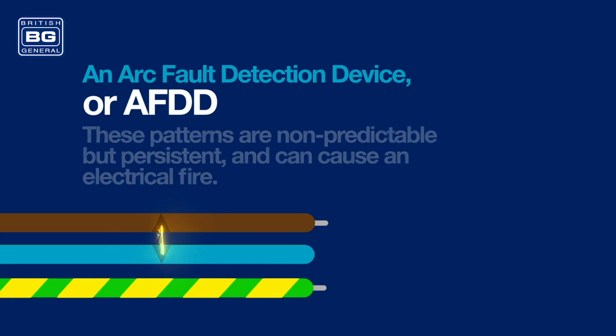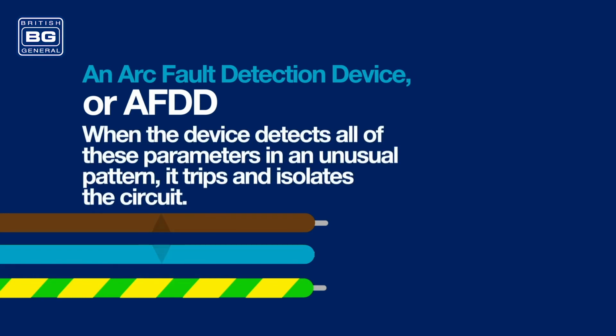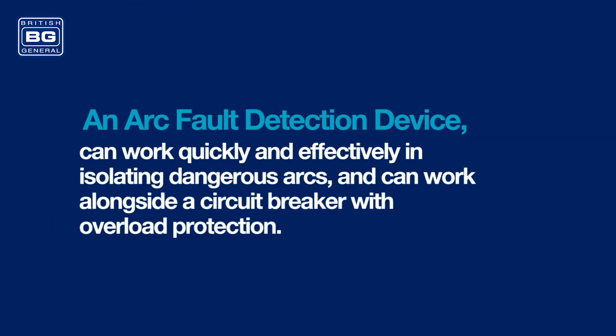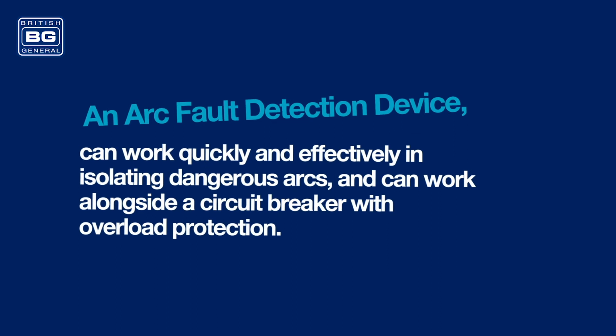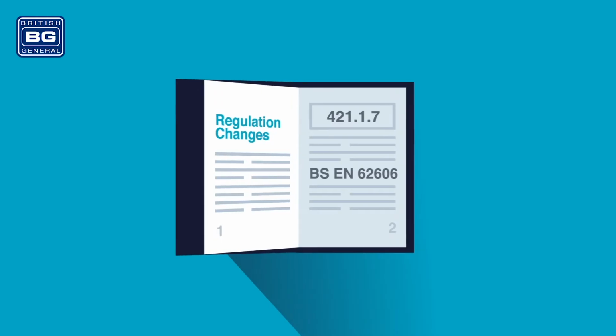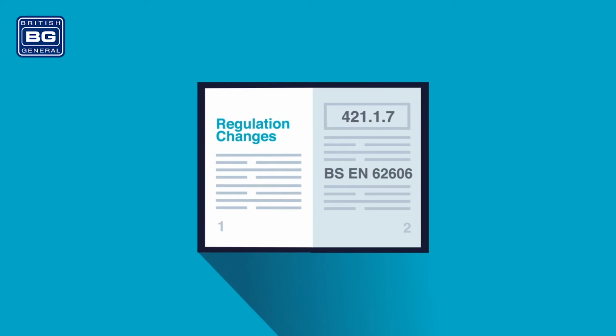An arc fault detection device can work quickly and effectively in isolating dangerous arcs, and can work alongside a circuit breaker or a residual current breaker with overload protection. Now you know what arcing is and how you can detect and isolate them. Where do you require an arc fault detection device? In the 18th edition, it only recommends the use of an arc fault detection device under the new regulation clause 421.1.7, which complies with BS EN 62606.